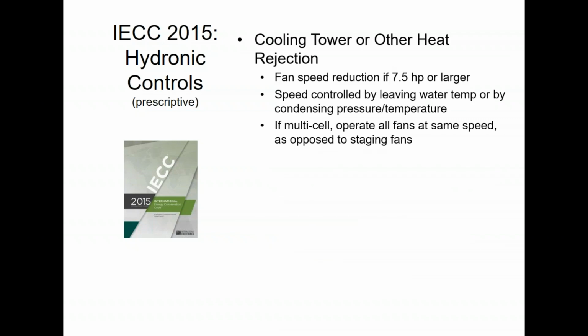Cooling towers, if you have 7.5 horsepower or larger, you have to have a way to reduce the fan speed. So that could be a VFD. I guess it could be a bunch of little tiny fans and stage them. You can do it that way, I suppose. But you have to have some way to control that airflow and reduce it down. You can control it by leaving water temperature if you want to. However, normally we, as a Carrier distributor, recommend that you do it based on the output of our chiller, which would be related to the condenser. We have an output on there specifically for head pressure control to send that over to the cooling tower to reduce the fan speed.